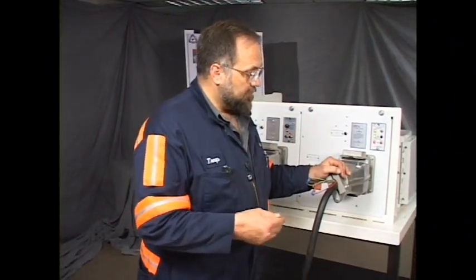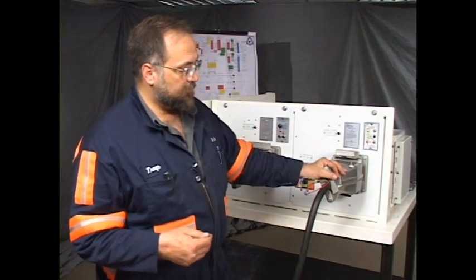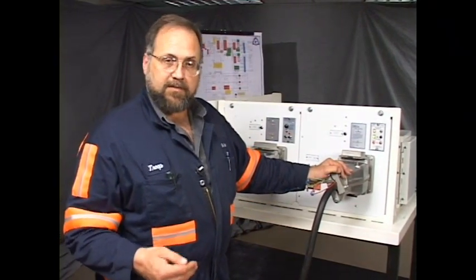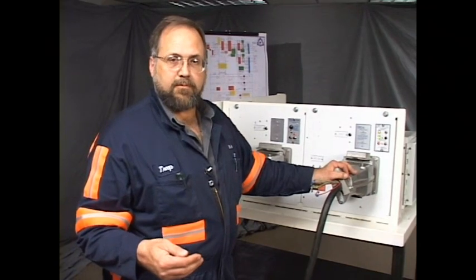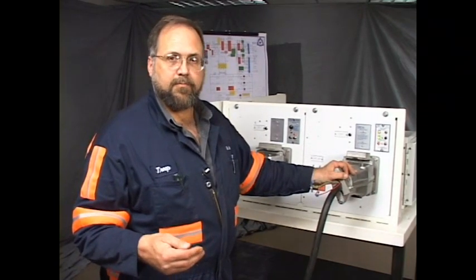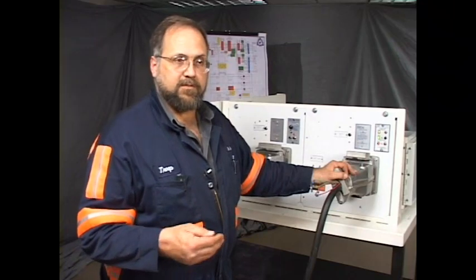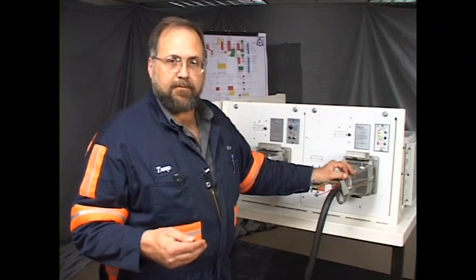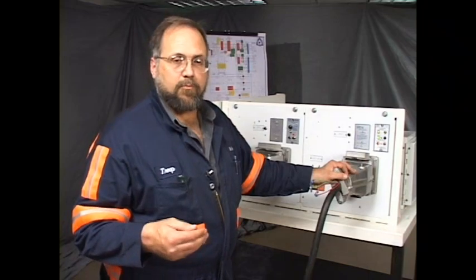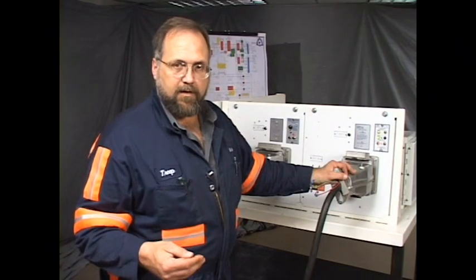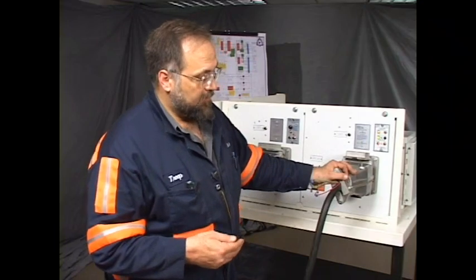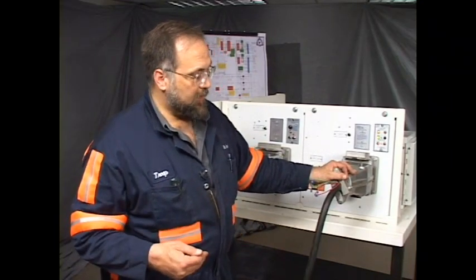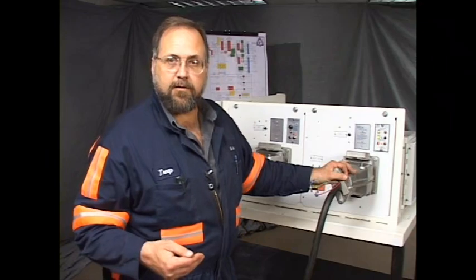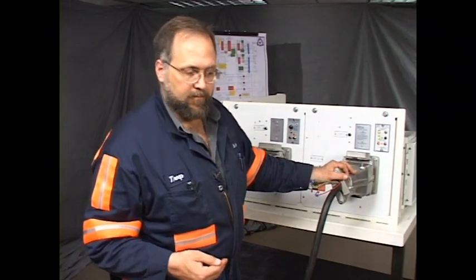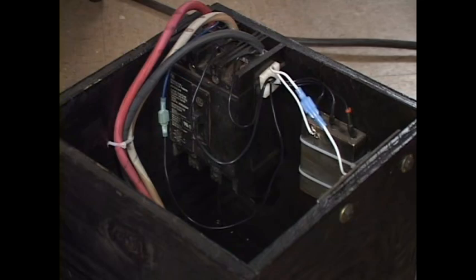On the machine there's another filter. It's identical to the first, and as its name implies, it filters any other noise off of the signal, like the 60 hertz power that we run. It filters that away, and it returns that signal cleaned up to the TRS common. On this particular unit it is a white wire. Frequently it's a green wire, the common wire from the filter. You can see that wire right here. That's this white wire that's standing up right here.